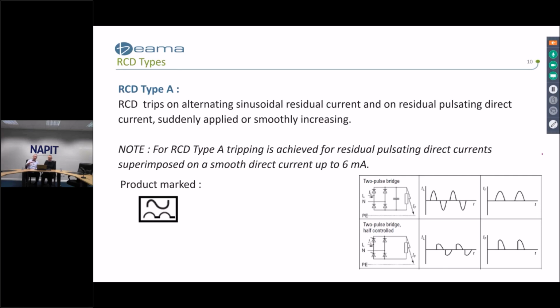And this effectively moves the zero point and can affect the operation of Type AC RCDs, but will not affect the Type A RCDs. For identification of Type A RCDs, a sine wave and half wave in a box is shown on the slide. This is marked on the front of the RCD.